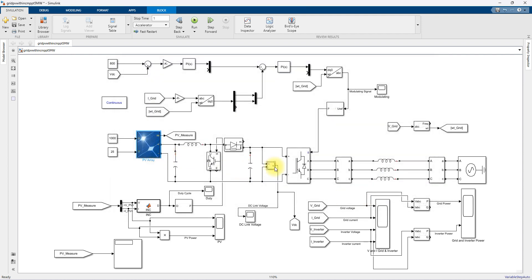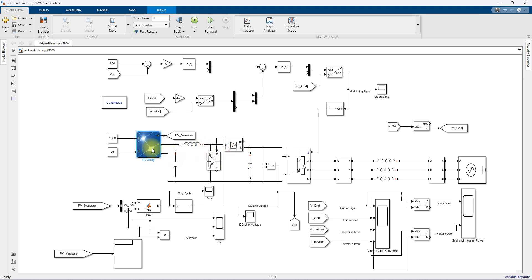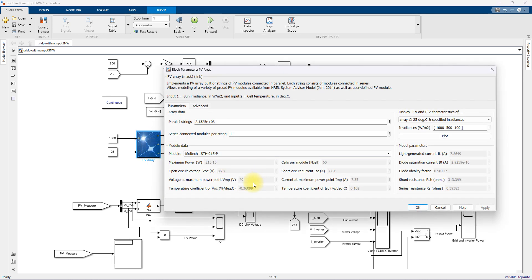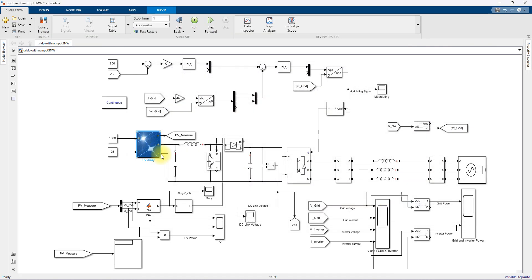The PV array will be connected to the grid inverter via a boost converter. This boost converter will be designed based upon the terminal voltage. At standard test conditions the terminal voltage will be 29 volts into 11, which is 319 volts across this PV array. The DC link voltage is going to be maintained at 800 volts.